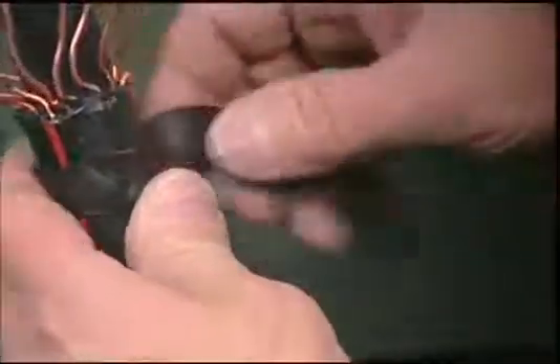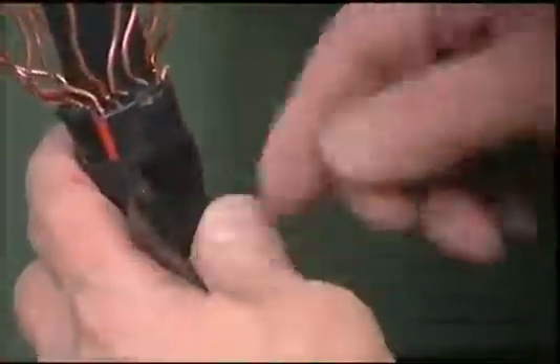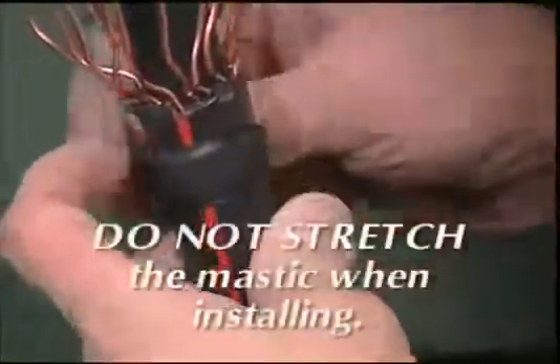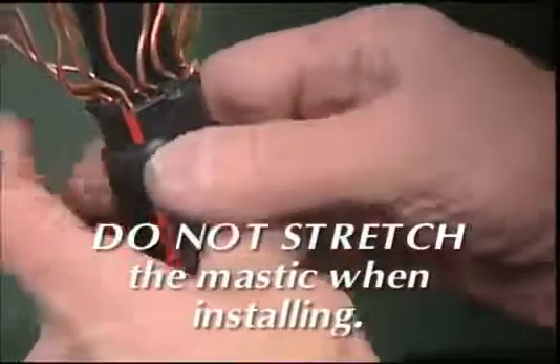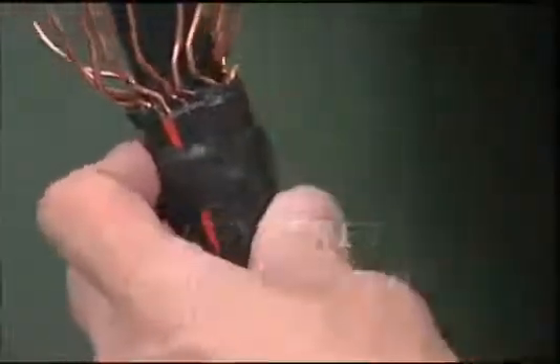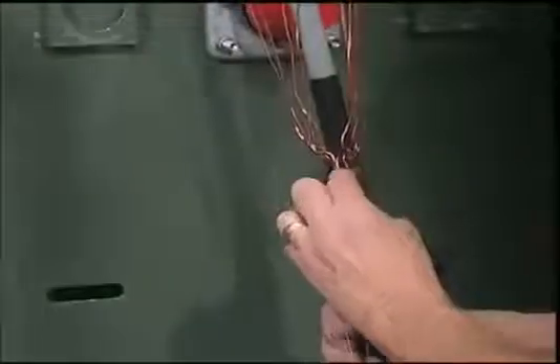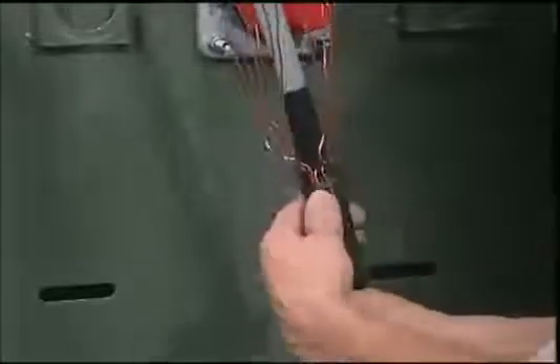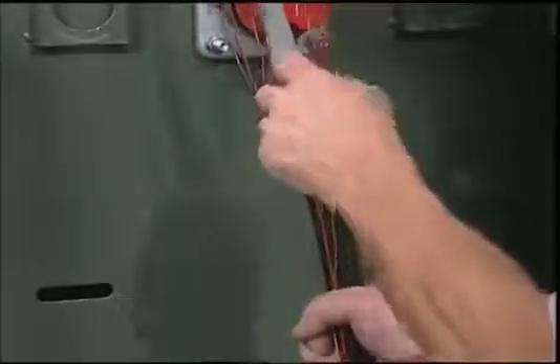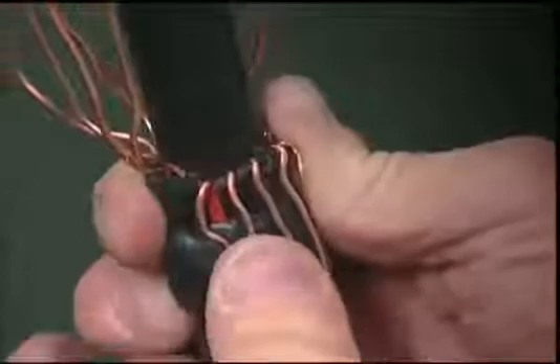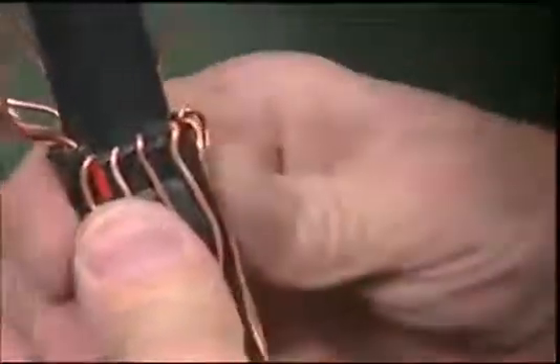Apply the first supplied mastic strip around the cable jacket, about 1/2 inch below the point where the jacket is removed. Do not stretch the mastic when installing. That's very important. Now, bend the concentric neutral strands back as tightly as possible against the cable, forming as small a radius as possible, and press the neutral wires into the mastic strip.